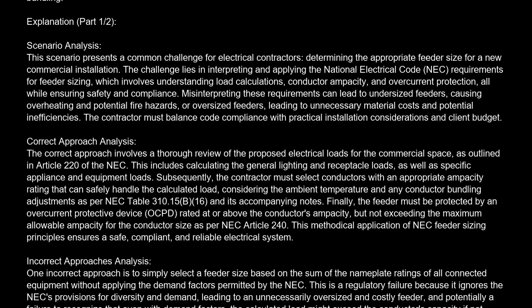Finally, the feeder must be protected by an overcurrent protective device, OCPD, rated at or above the conductor's ampacity, but not exceeding the maximum allowable ampacity for the conductor size as per NEC Article 240. This methodical application of NEC feeder sizing principles ensures a safe, compliant, and reliable electrical system.